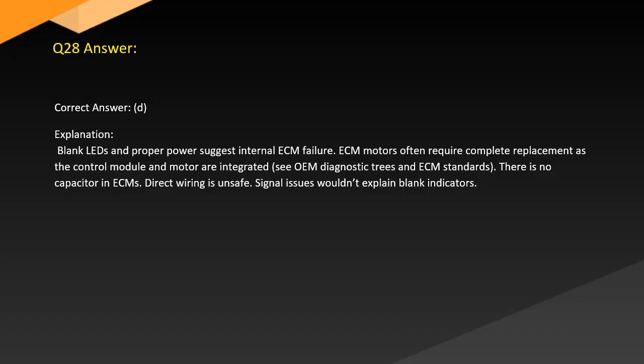Answer. Correct answer, D. Explanation. Blank LEDs and proper power suggest internal ECM failure. ECM motors often require complete replacement as the control module and motor are integrated. See OEM diagnostic trees and ECM standards. There is no capacitor in ECMs. Direct wiring is unsafe. Signal issues wouldn't explain blank indicators.